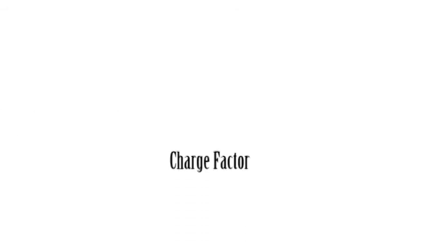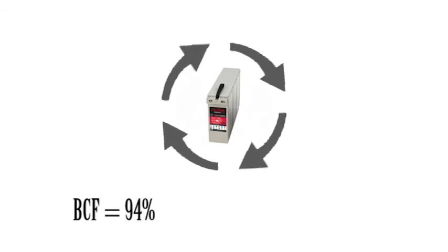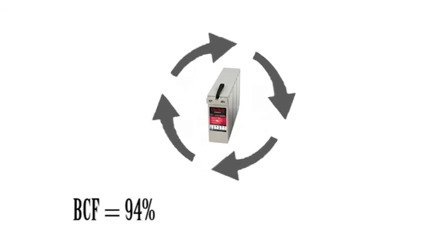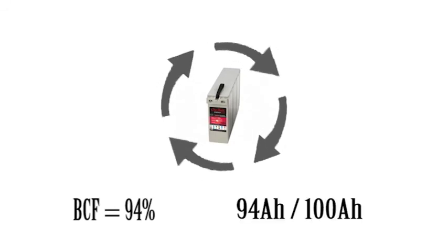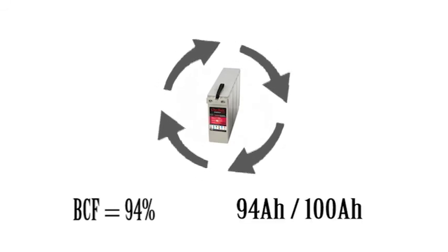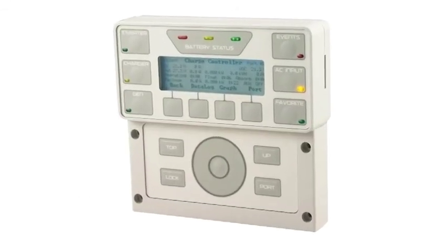Step 5, charge met time. This is a user adjustable setting, but usually 1 minute is optimal. Step 6, charge factor, which must be validated. This value is to compensate for the losses in the recharge of the batteries. For example, using a charge efficiency factor of 94%, the FNDC will only count 94 amp hours out of 100 amp hours. You are now done programming your FLEXnet DC.